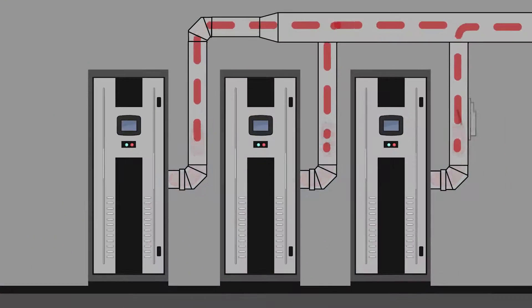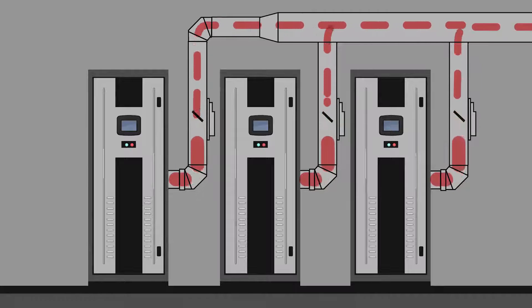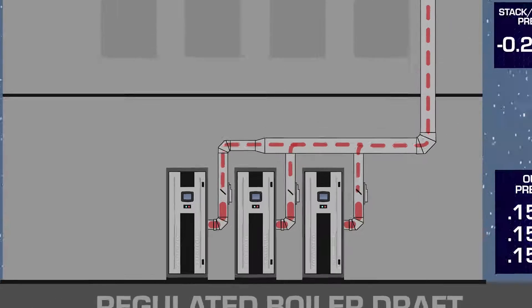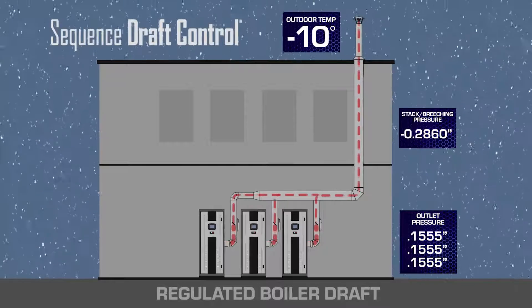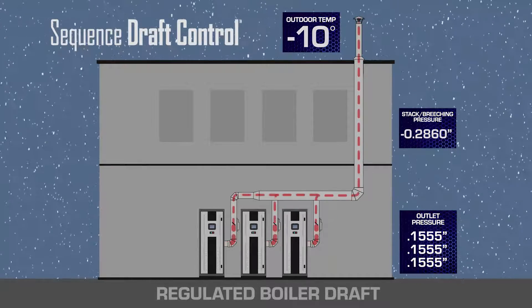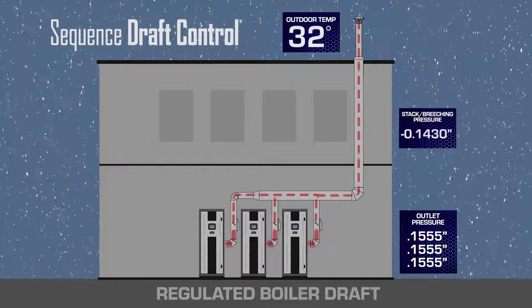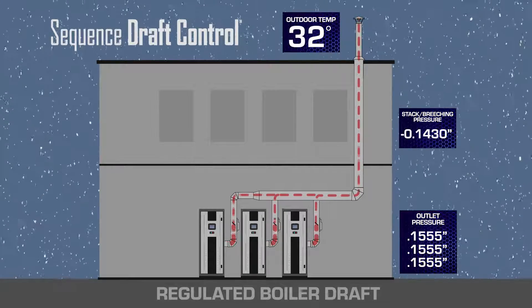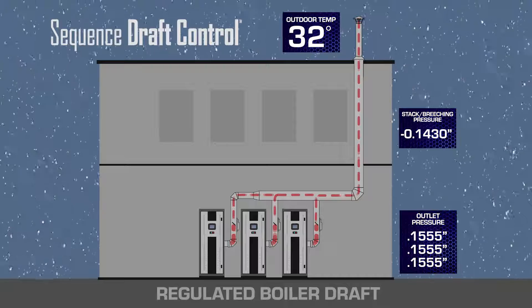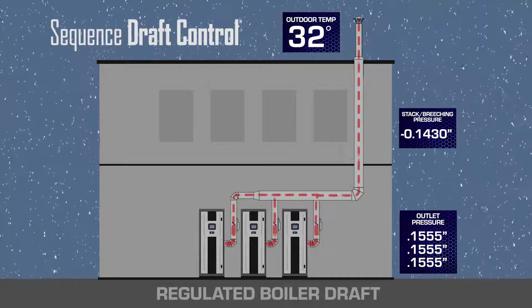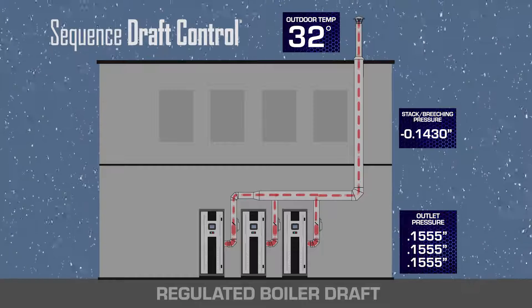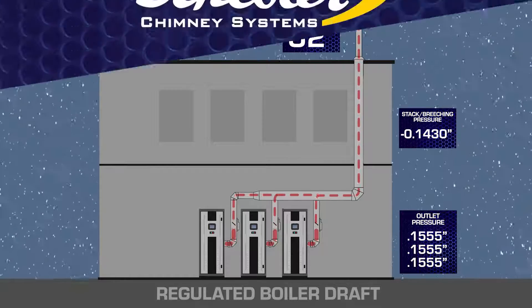If we apply Schebler sequence draft control dampers to a common vented system, we're able to monitor and control each appliance's outlet pressure independently of the stack pressure reading. This allows us to have Category 4 operation in a common vented system and automatically compensate for various firing rates and ambient temperatures to maintain maximum efficiency at all times.